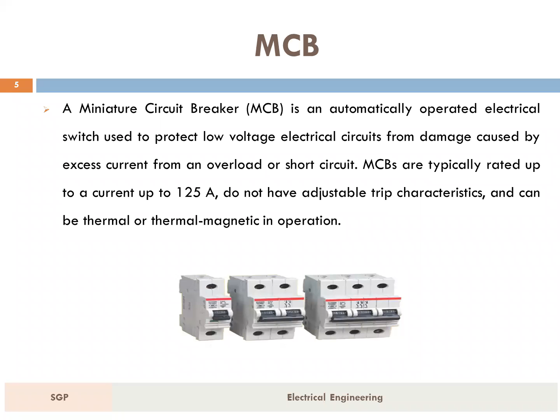MCB is the miniature circuit breaker, which is an automatically operated electric switch used to protect low voltage electrical circuits from the damage caused by excess current from an overload or a short circuit. MCBs are generally rated up to a current of 125 ampere. In the MCB, there is no adjustable trip characteristic, which can be thermal or thermal magnetic. In the figure, we can see the different types of MCB.